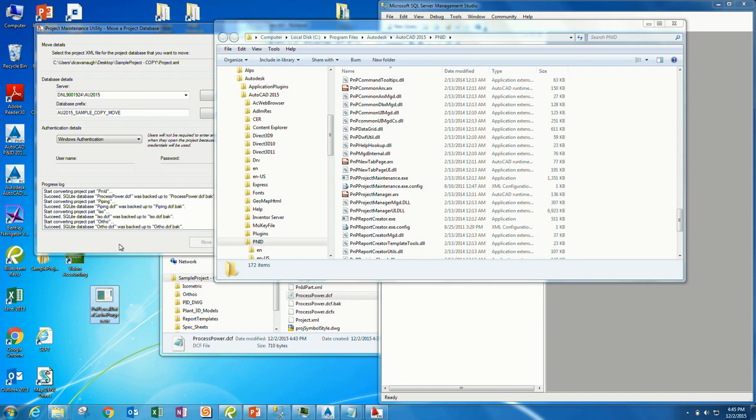It could prevent those little hiccup issues. When you open a drawing file, Plant will store a local instance of that drawing file while you have it open on your machine. When you save it, it then updates the SQL Server. It can have something like a 30 megabit cache, and I've experienced issues in the past, more with 2013, 2014 P&ID, that they kind of resolved. But it's a good habit to clear the cache, start fresh, and pull all your information from the database, so you don't risk any duplicate or old pieces of information finding their way in.